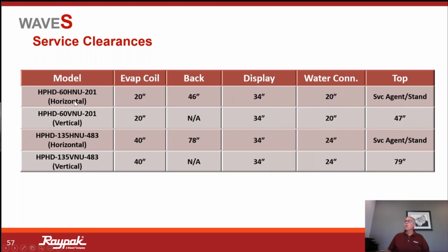Also on the horizontal units that discharge vertically, the air intake comes in on the horizontal and they discharge vertically. We need to have room on top of that so that if we were ever to have to access that fan, right? So they say in the manual to leave enough room for an agent to stand on it. I'm not sure how to extrapolate that from a service side, so maybe some of my colleagues have some understanding, but I guess the height of the agent is how much room you need to leave there to be able to access and get above that unit.